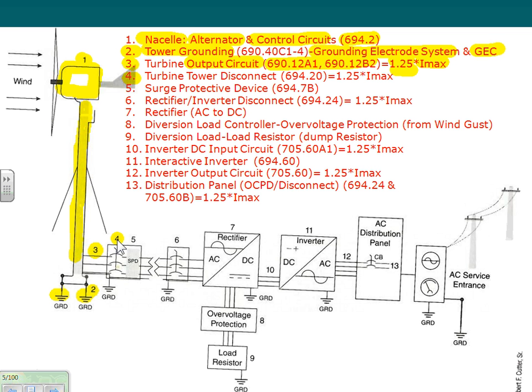This is no different. They require you to have a disconnect here. So that disconnect is going to be number 4, and they call it the tower disconnect. And how do you size this disconnect? The same thing. You take the full load amps of that turbine and multiply by 1.25. Say you came up with 50. They don't make a 50 disconnect. The next standard size is 60. You put a 60 amp disconnect. What's the voltage? Say it's a 600 volt disconnect, NEMA 3R.